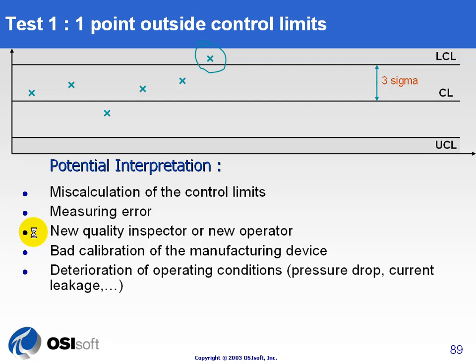The first thing most people think of immediately is deterioration of operating conditions. It could be that, or it could be some of these measurement errors, but it could, in fact, be that your operating conditions are going bad on you. You're not running the process the way you should be, and now is the time to change your target limits or change control in some way. Remember that the point of waiting for three standard deviations is so that people won't over-control. In operations, people tend to over-control rather than under-control. We want to make sure that people don't do anything until they see something that really indicates an assignable cause variation. You could also have inadequate raw material, or simply new instrumentation measuring error.